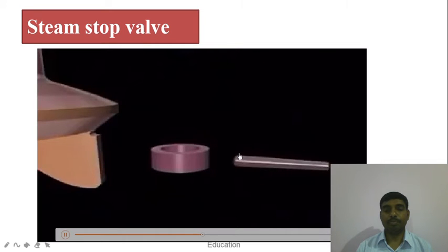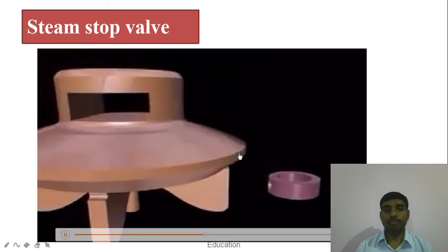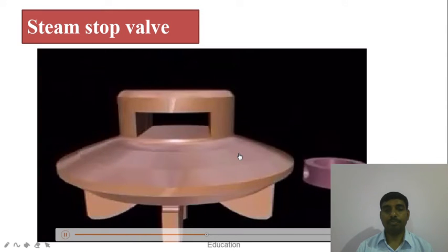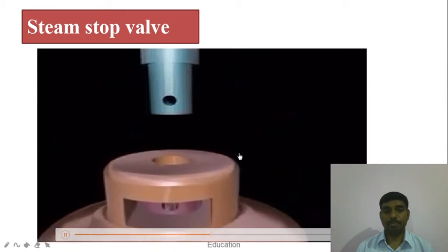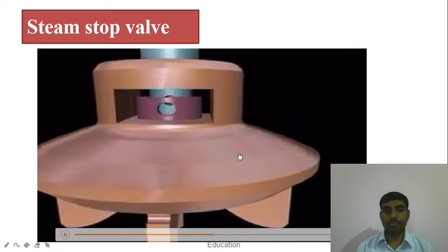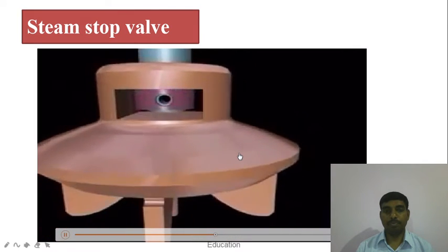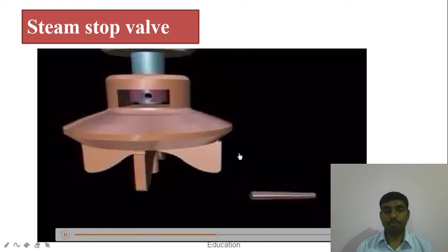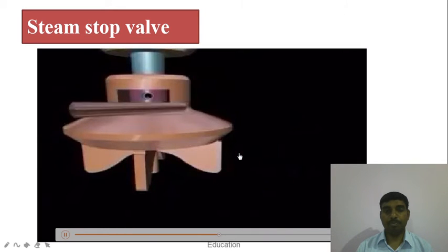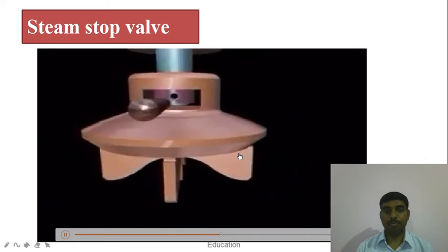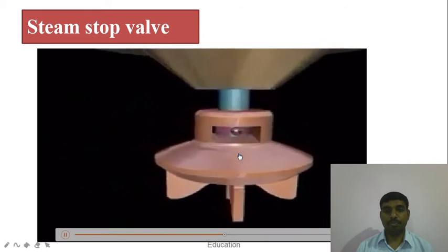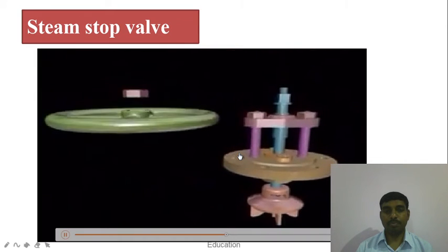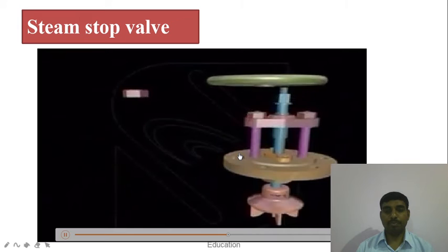The other end of the spindle is stepped to assemble it with the valve. The spindle is inserted through the bridge and the cover assembly. The collar is introduced into the valve slot. The spindle step is inserted into the valve and it is fastened with the collar using the cotter pin. Thus, the spindle will carry the valve along with it when it is raised or lowered.